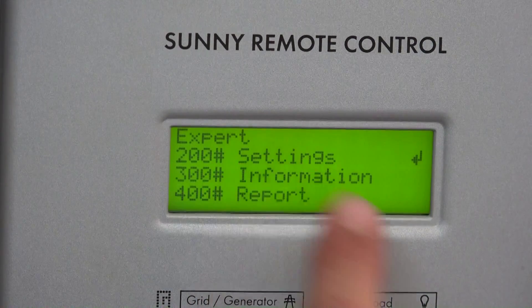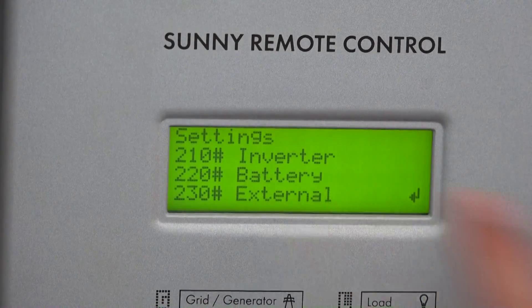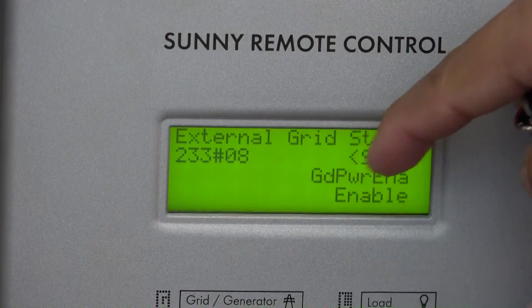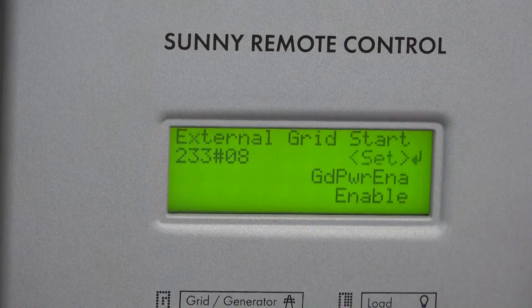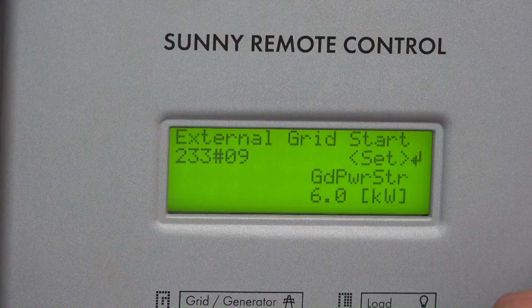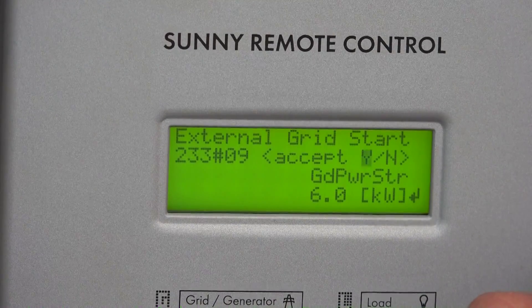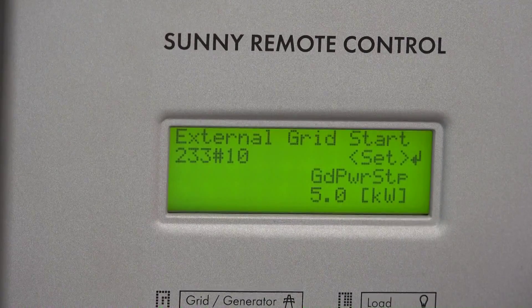We're in expert mode. Go to 200 settings, then external, then parameter 233 grid start — turn the knob until you see 'enable grid power'. Enable it. Then go to the next page: 'power start when external grid start'. When the load is more than 6 kilowatt, the grid will take over — set that to 6. If you want lower, set it to 5. Then 'grid power stop' — set that to 5 as well.